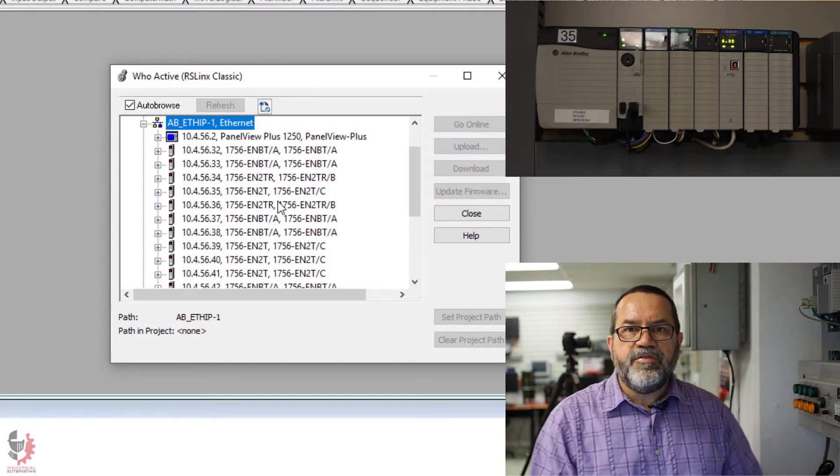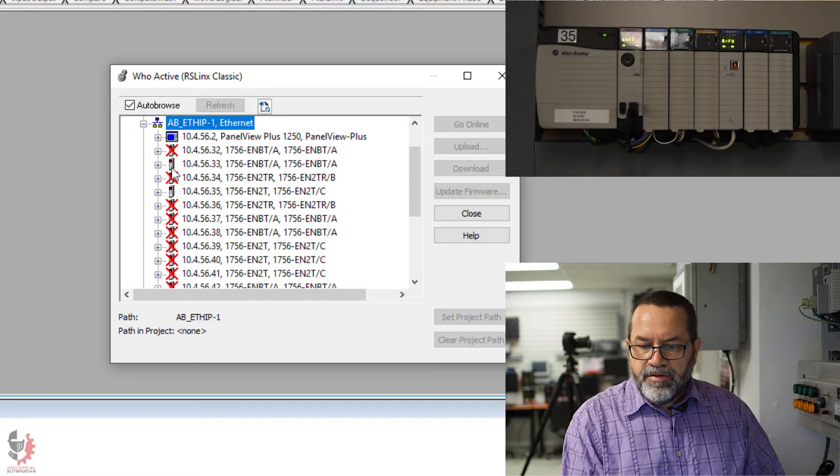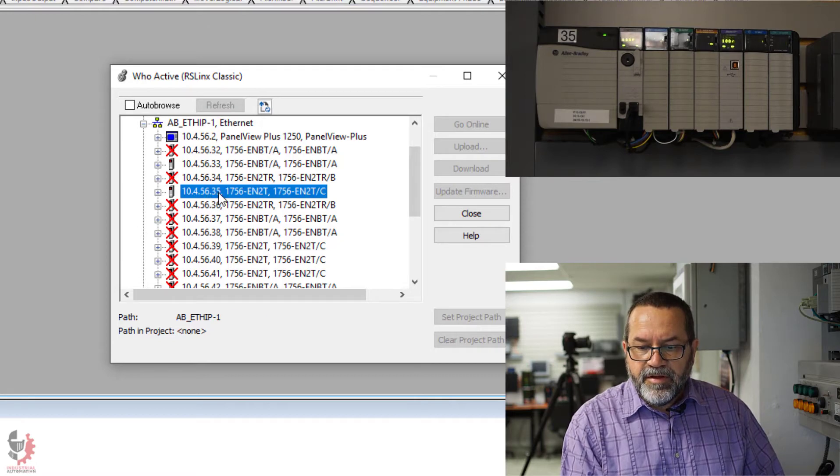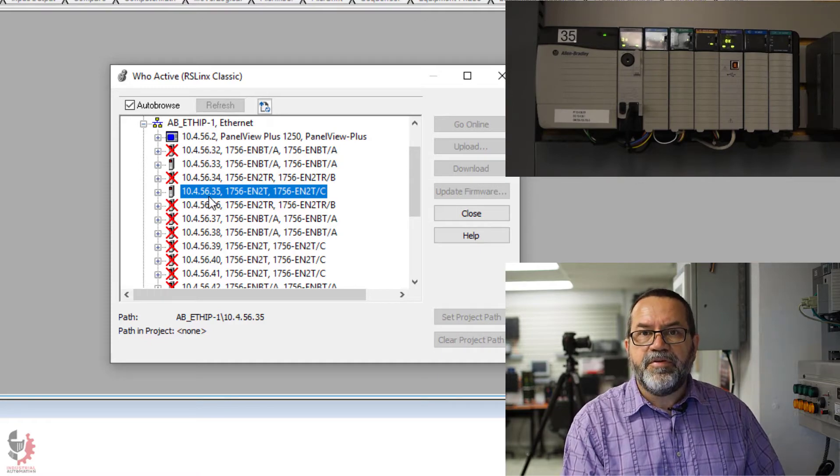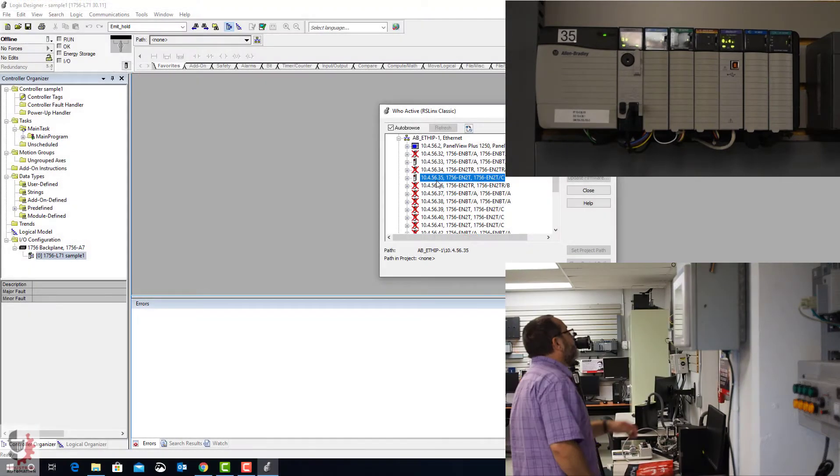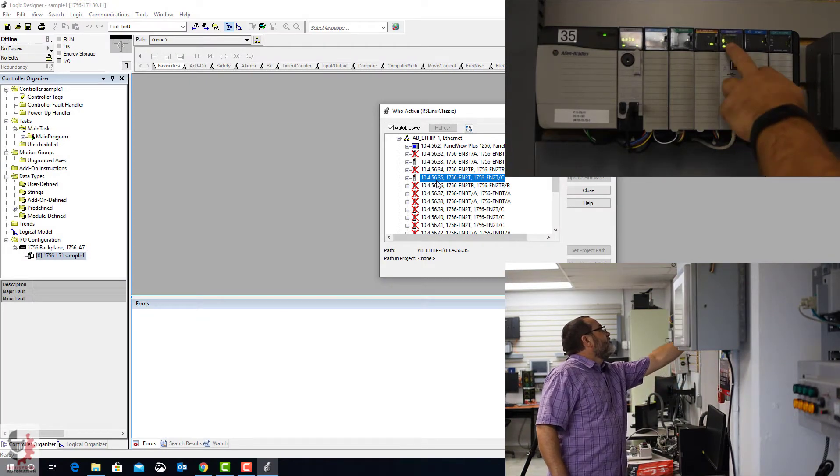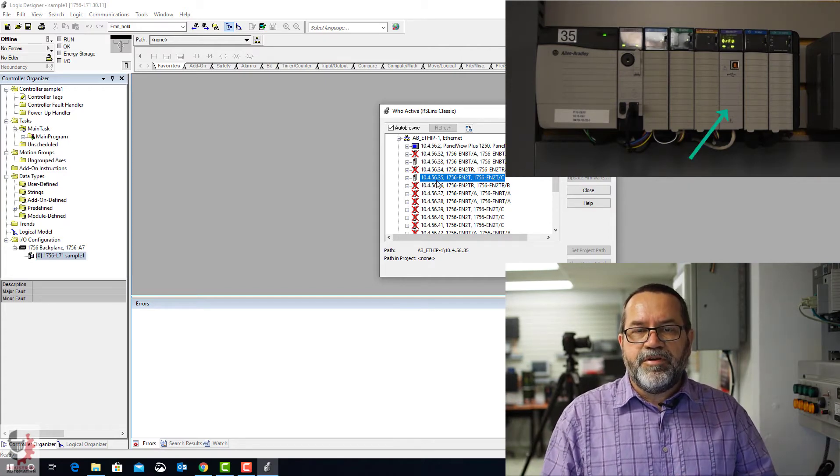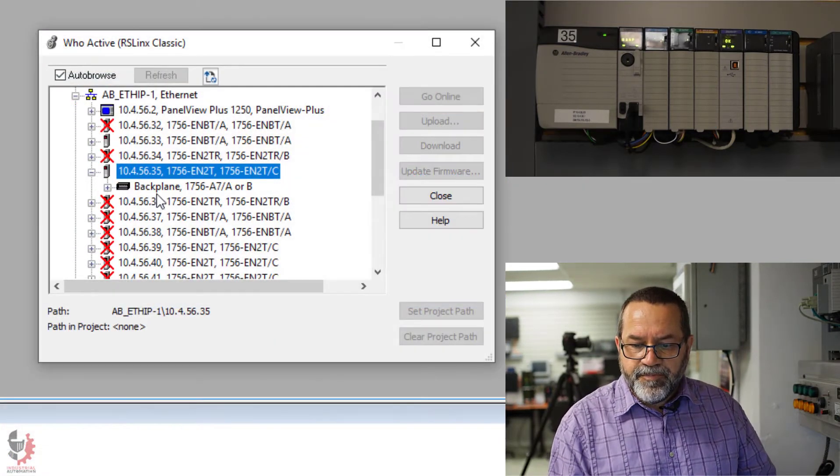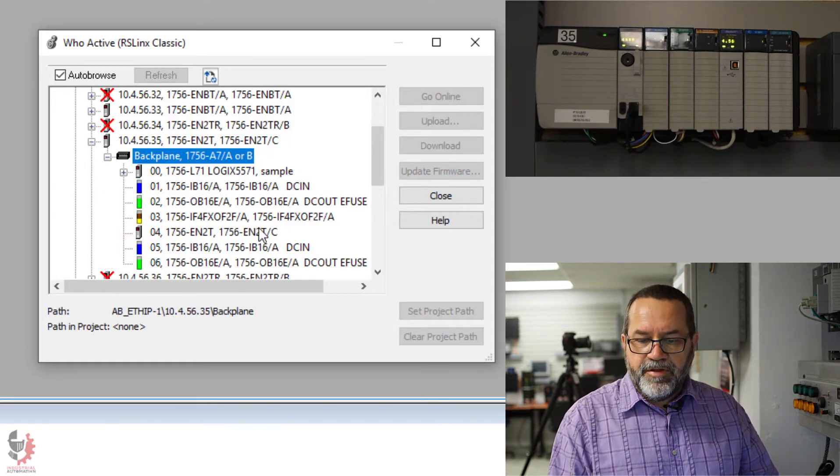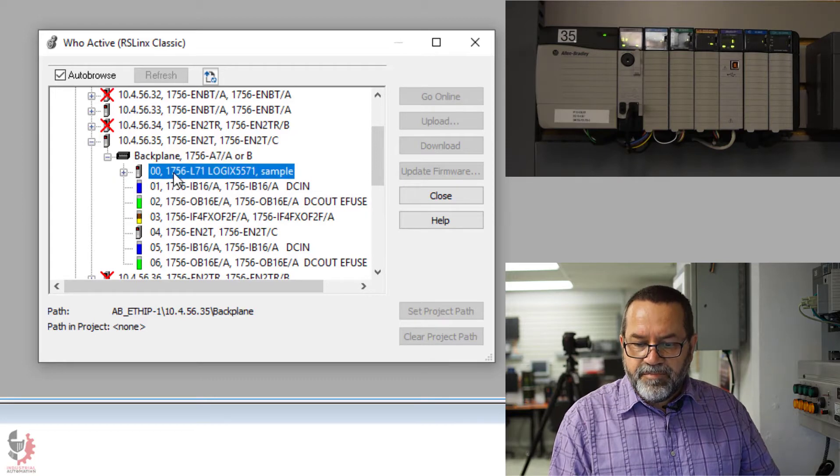And I want to use Ethernet IP to communicate, so I'll expand that. And this is going to show every PLC in the lab. Notice in the lab here, some are X'd out, and that's just because the power's not turned on. And I wanted to talk to number 35, so 10-4-56-35. I get that from the communication module. So it's showing some status, 10-4-56-35. So that's my IP address. That's the IP address of the communication card. I can't talk with the communication card. I can only use it as a pathway to the controller. I'm going to expand that, and now I can see the backplane. Expand it again. And now I can see everything that's on that PLC.